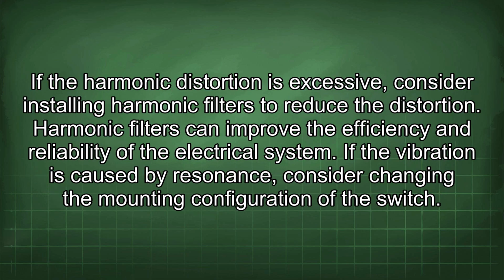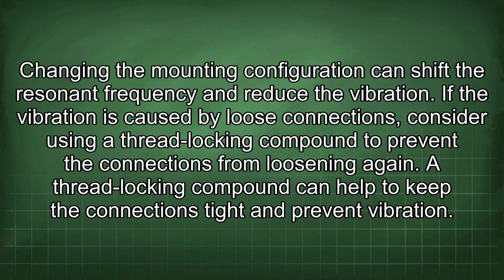If the harmonic distortion is excessive, consider installing harmonic filters to reduce the distortion. Harmonic filters can improve the efficiency and reliability of the electrical system. If the vibration is caused by resonance, consider changing the mounting configuration of the switch. Changing the mounting configuration can shift the resonant frequency and reduce the vibration.